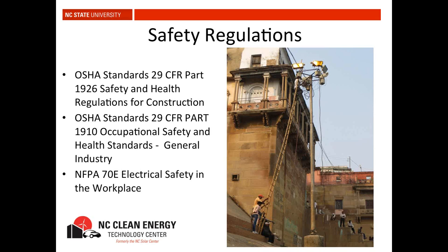When you're installing a PV system — putting modules on the roof, climbing up and down ladders — you comply with Part 1926 for construction. General industry standards apply to things like warehouse work or operations and maintenance, which is not construction. The general industry standards are stricter in some ways: fall protection is required at more than six feet in construction, but only four feet in general industry.